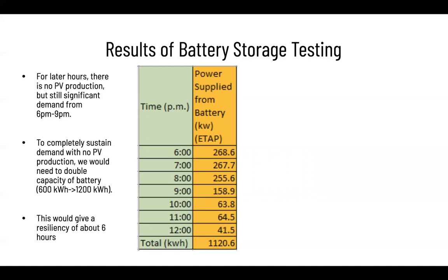In order to completely sustain the demand during these hours, we would suggest doubling our capacity of the battery storage to about 1,200 kilowatt hours. That would give us a resiliency of about 6 hours, which is more than what we had initially hoped for. We could get by on about 3 hours during this peak time with 0 PV production.